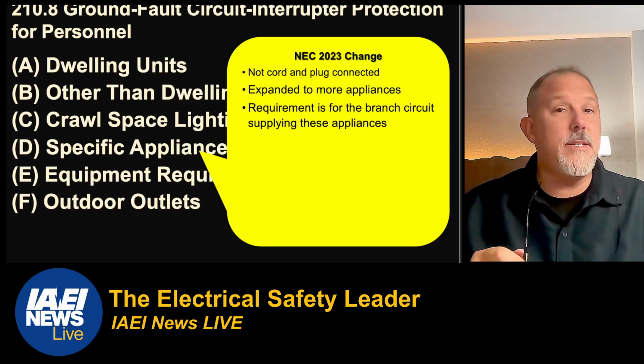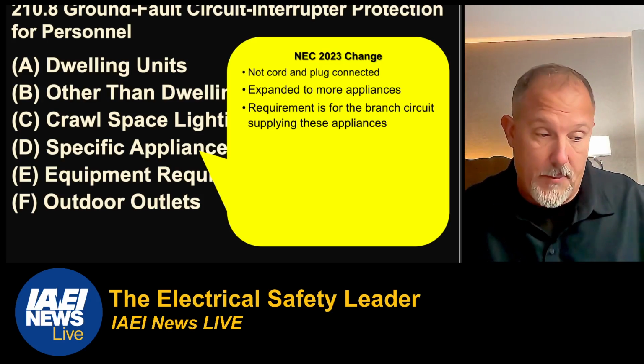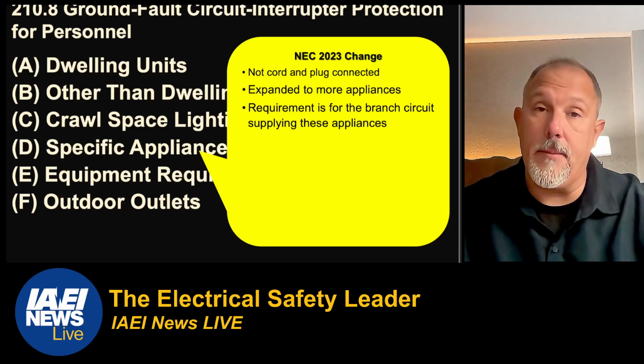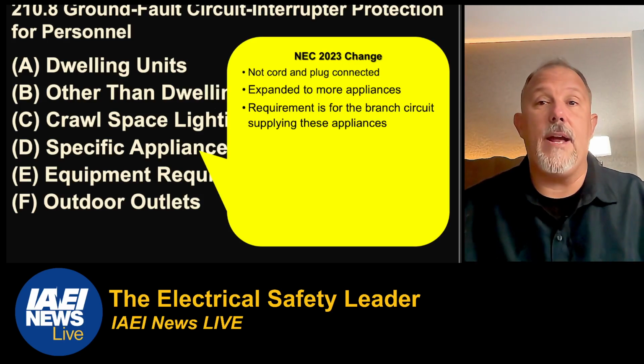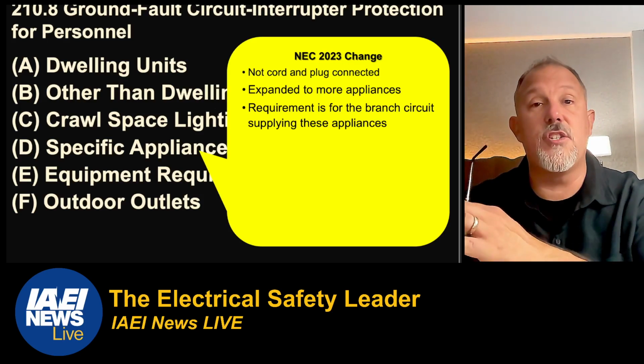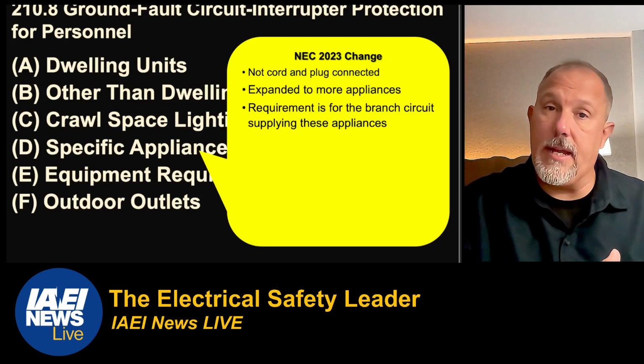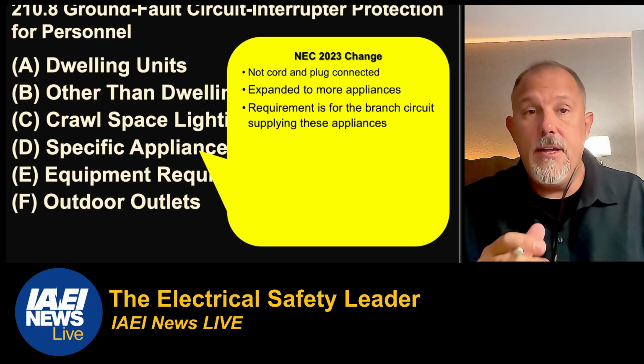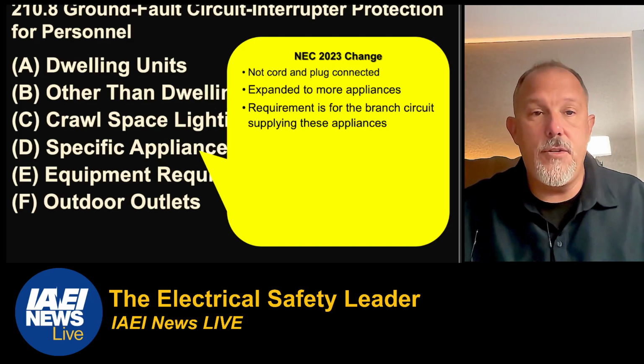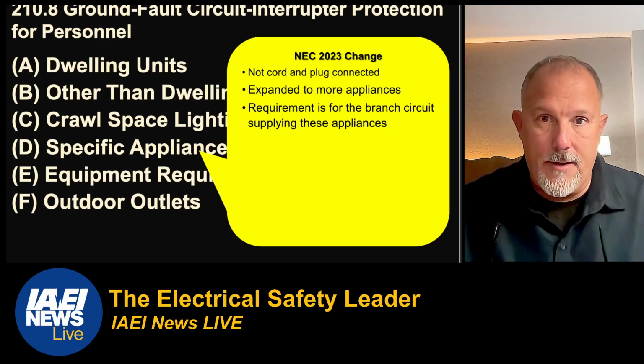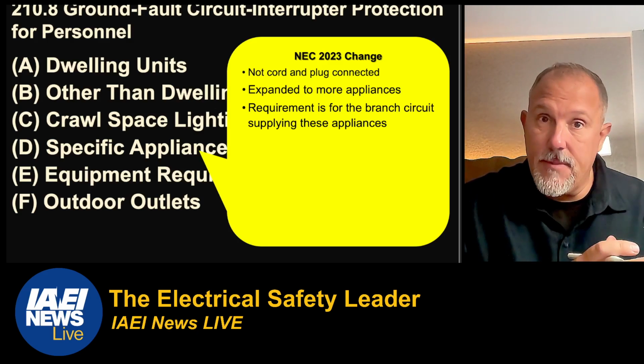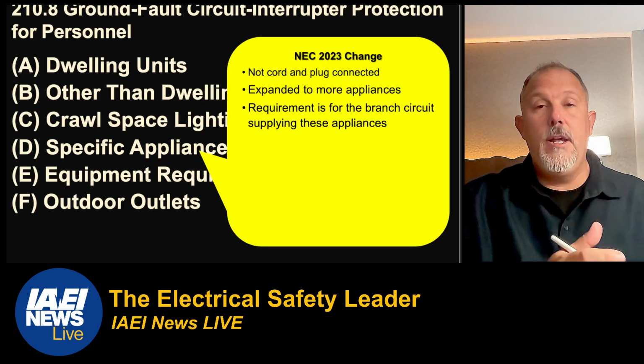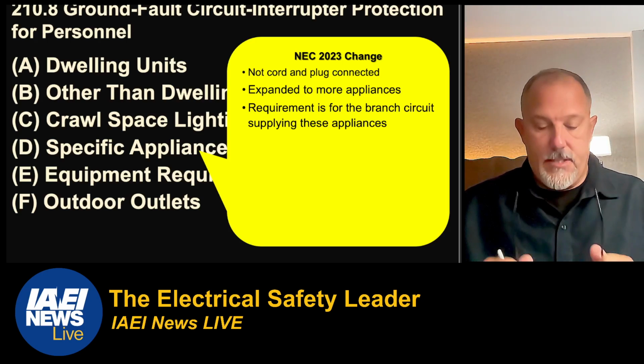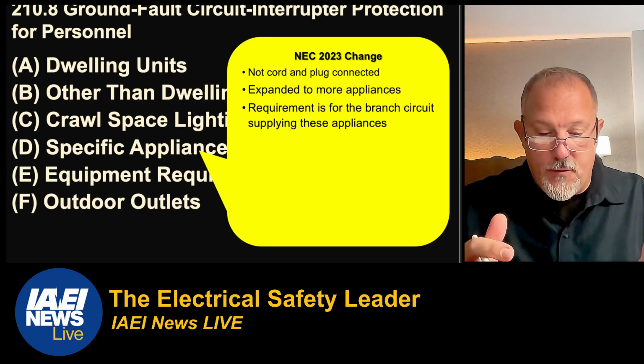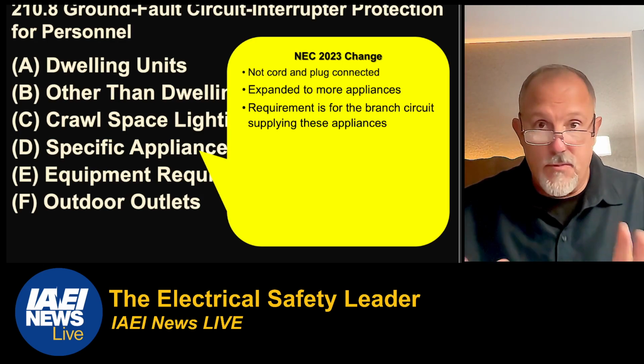And there are different opinions on this one, and I hesitate to even give you my opinion. But just look at 422 and think about what its scope of work is. Think about Article 210 and what its scope of work is. And I can tell you that the requirements we're talking about in 210.8(D) are focused on the branch circuit, because that's the scope of 210. The focus is on the branch circuit or an outlet, not a receptacle.